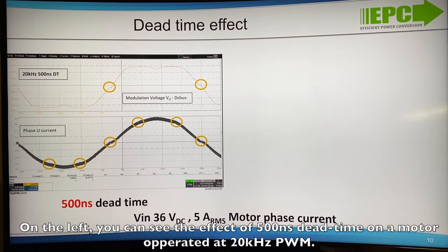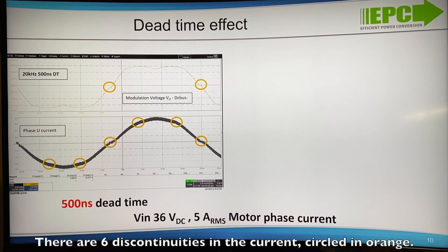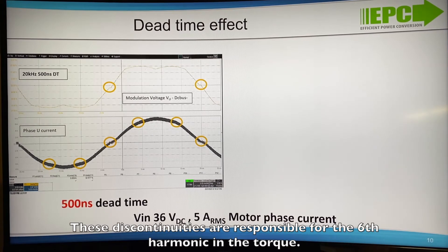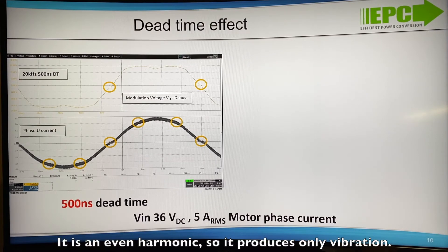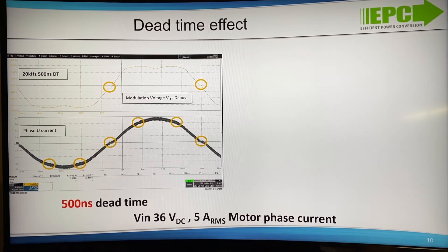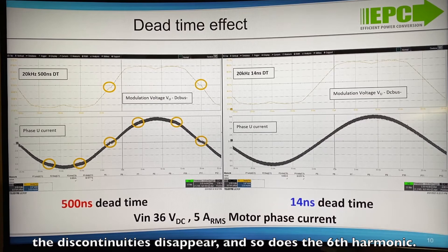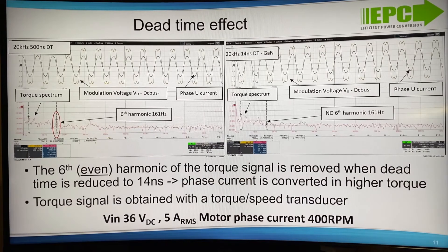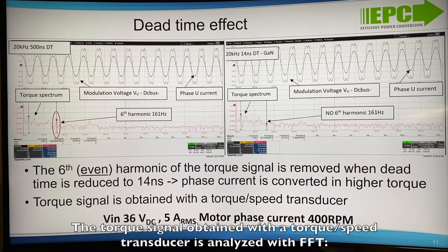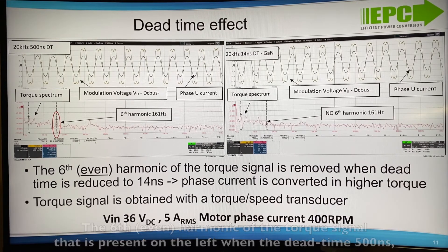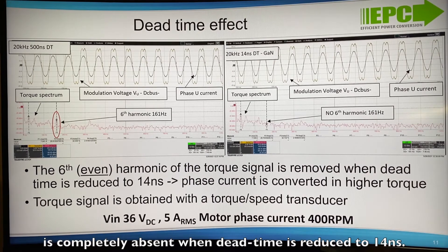On the left you can see the effect of 500 ns dead time on a motor operated at 20 kHz PWM. There are 6 discontinuities in the current, circled in orange. These discontinuities are responsible for the 6th harmonic in the torque — it is an even harmonic, so it produces only vibration. On the right you can see that by reducing the dead time to 14 ns the discontinuities disappear, and so does the 6th harmonic. The torque signal obtained with the torque speed transducer is analyzed with FFT. The 6th even harmonic of the torque signal that is present when the dead time is 500 ns is completely absent when the dead time is reduced to 14 ns.